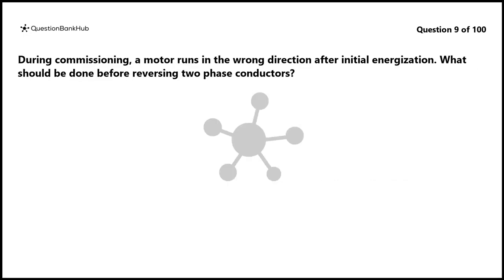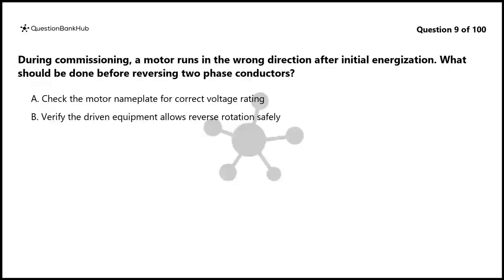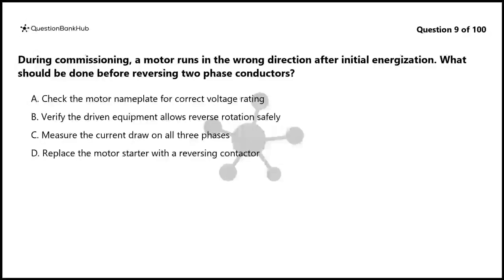Question 9. During commissioning, a motor runs in the wrong direction after initial energization. What should be done before reversing two-phase conductors? A. Check the motor nameplate for correct voltage rating. B. Verify the driven equipment allows reverse rotation safely. C. Measure the current draw on all three phases. D. Replace the motor starter with a reversing contactor.